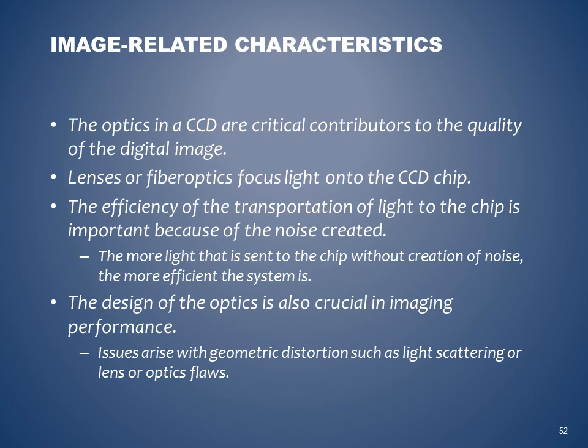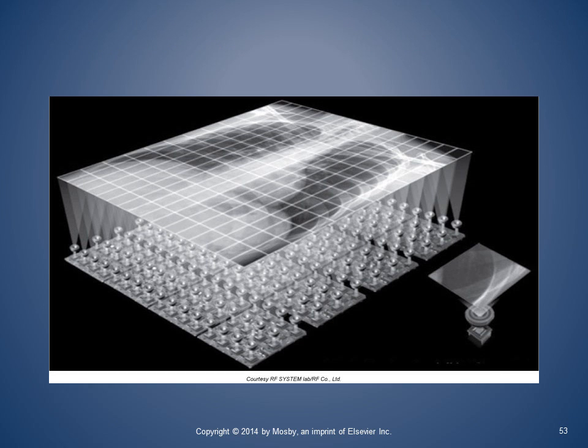Image-related characteristics. The optics in a CCD are critical contributors to the quality of the digital image. Lenses or fiber optics focus light onto the CCD chip. The efficiency of the transportation of light to the chip is important because of the noise created. The more light that is sent to the chip without creation of noise, the more efficient the system is. The design of the optics is also crucial in imaging performance. Issues arise with geometric distortion, such as light scattering or lens and optics flaws.